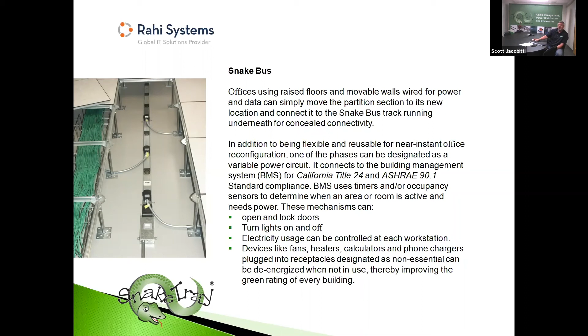One of the other really cool things about Snake Bus is its ability to be switched. So we do have 3 phases coming into the track itself, and we can turn off and on any of these phases. So as we're looking at, say, Title 24 in California, or more on a national level ASHRAE 90.1 for energy efficiencies, we do have the ability to both digitally and analog with some switches turn power off to different areas of the office space. So we have occupancy sensors that are coming back to the building management software system. No one's here, we can shut those particular units off. On a daily basis, at the end of the day, we can turn off all the non-essential power. So it does maintain complete compliance with California Title 24 as well as ASHRAE 90.1.